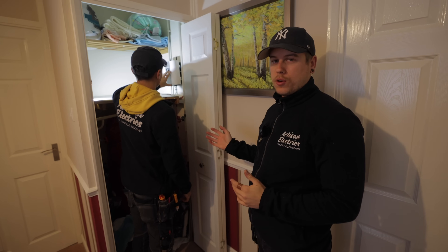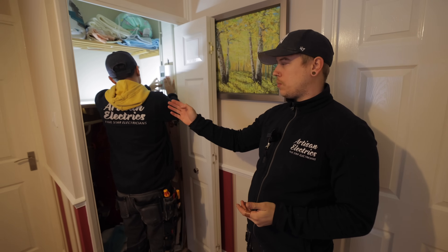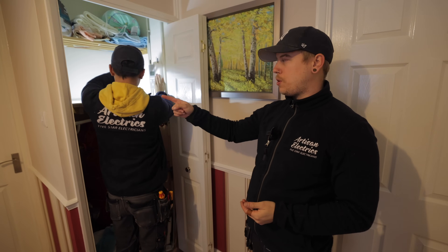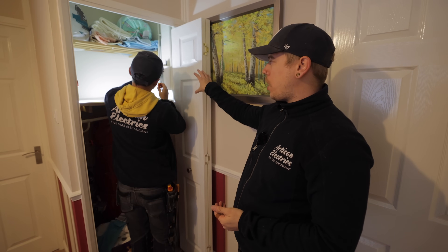With the Eddi you don't actually have to install anything new to your fuse board. It literally just comes off your double pole isolator, which used to go straight into the immersion — you just wire it into the Eddi first, and then that diverts into the immersion tank.